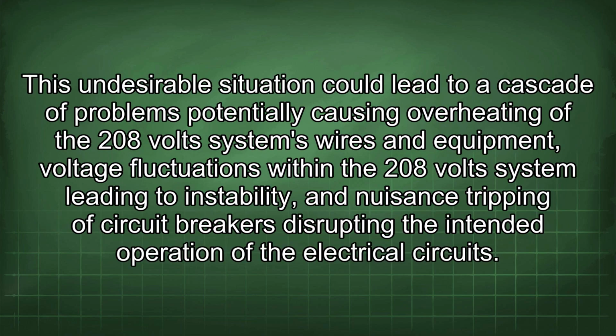This undesirable situation could lead to a cascade of problems, potentially causing overheating of the 208 volts system's wires and equipment, voltage fluctuations within the 208 volts system leading to instability, and nuisance tripping of circuit breakers, disrupting the intended operation of the electrical circuits.